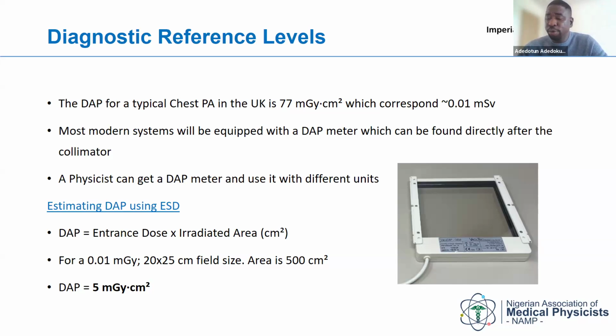If your equipment does not even give DAP, then you can get a DAP meter. I've put a picture here, which is this one, and that is a DAP meter. You can incorporate this and it measures your DAP for you, because it's so easy to calculate your DRL. Your DRL is either based on DAP or based on entrance skin dose. So if you don't have a DAP, it becomes a bit more cumbersome, but not so cumbersome.